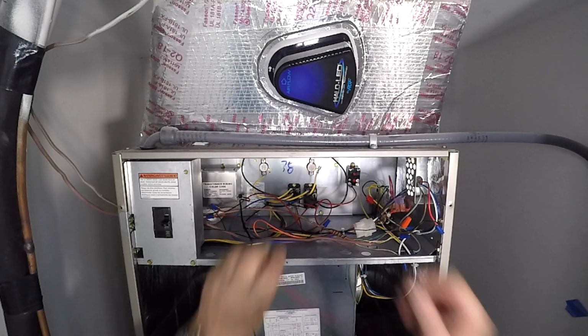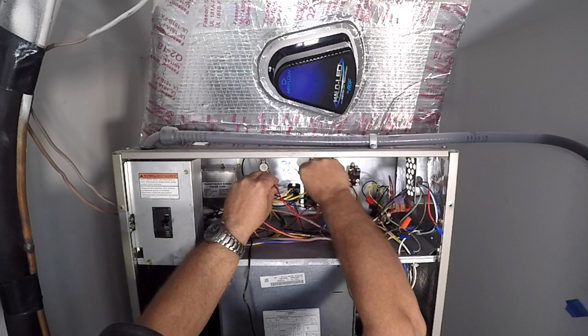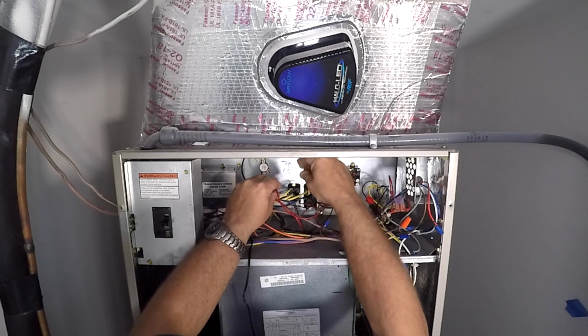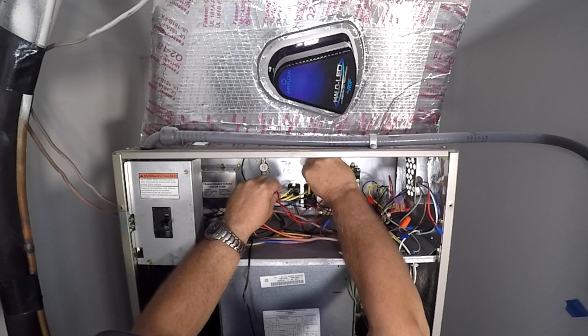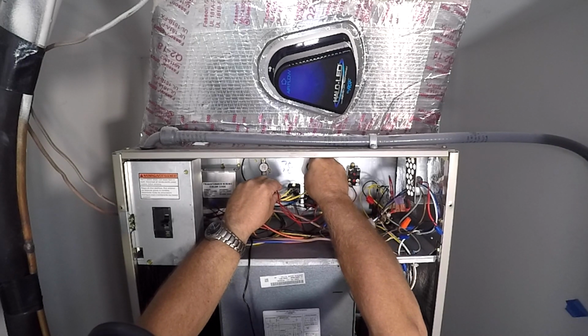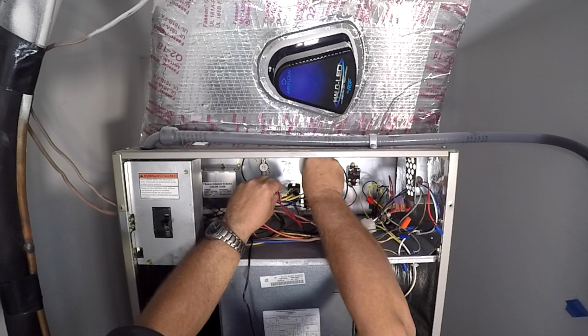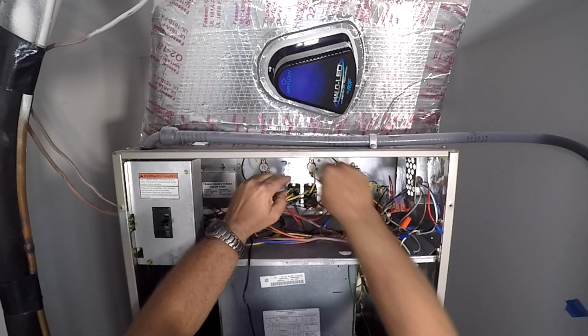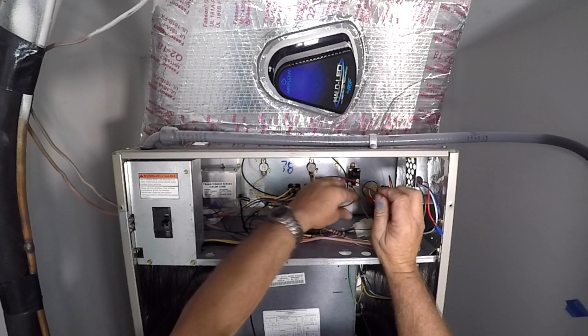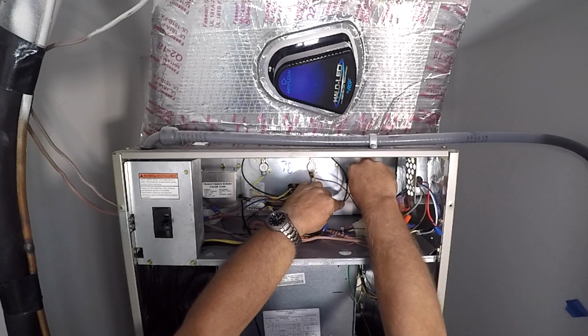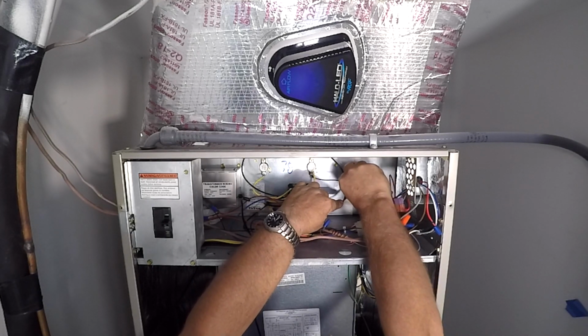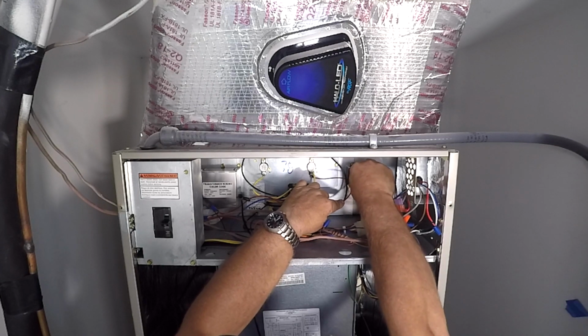So we're going to place that on where our heat sequencer turns on, or in this case the relay. So this is the line voltage when the unit turns on the heat. And then we're going to take our little jumper. It's going to go to terminal 5 on this particular unit.